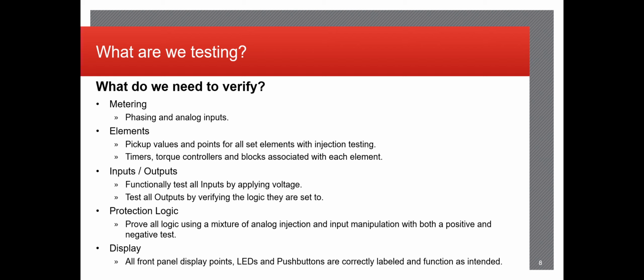So what are we testing? In this example, when we're logging into the relay for the client, we're going to be looking at specific elements that the client's looking for. Certain stuff, metering, which is the phasing and analog inputs, measuring the current voltages as well as the phase angles of each of them. Specific relay elements such as pickup values and points for all set elements, timers, torque controllers, and blocks associated with each element as well. The inputs and outputs, the functionally tested inputs by applying voltages and testing all the outputs by verifying the logic they are set to.